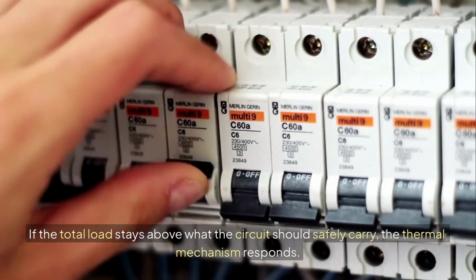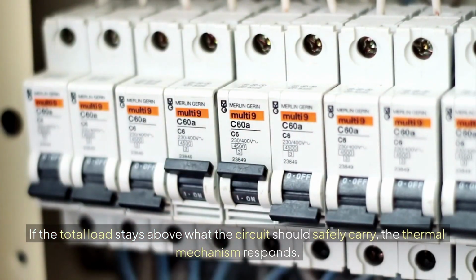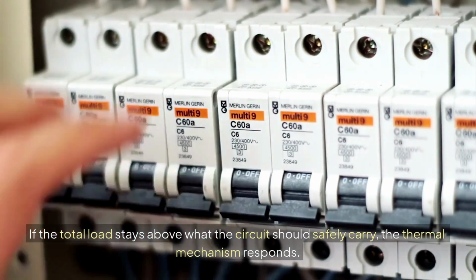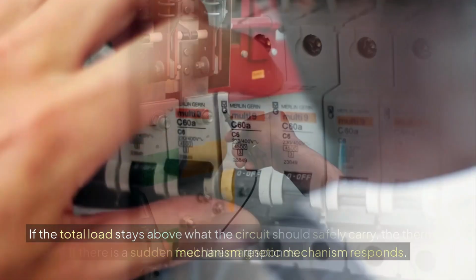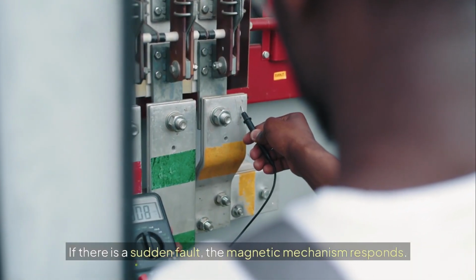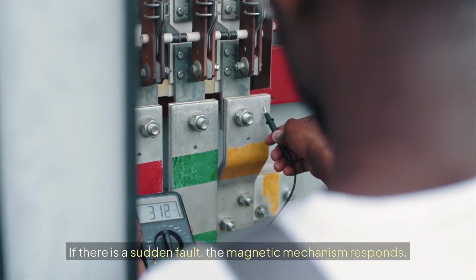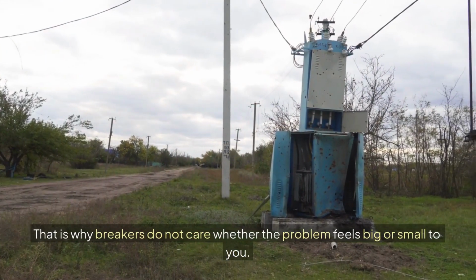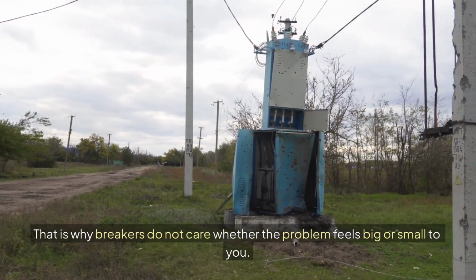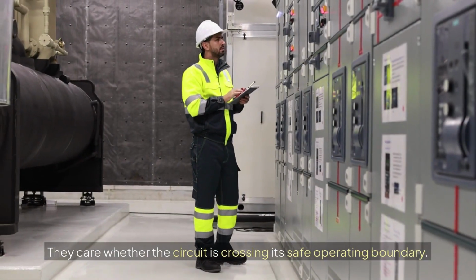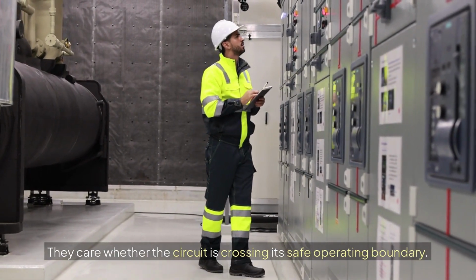If the total load stays above what the circuit should safely carry, the thermal mechanism responds. If there is a sudden fault, the magnetic mechanism responds. That is why breakers do not care whether the problem feels big or small to you. They care whether the circuit is crossing its safe operating boundary.